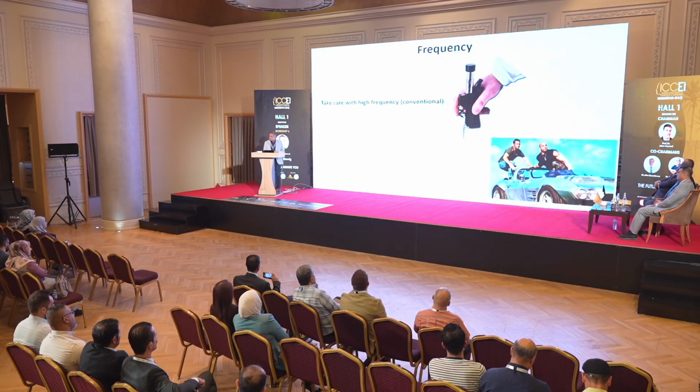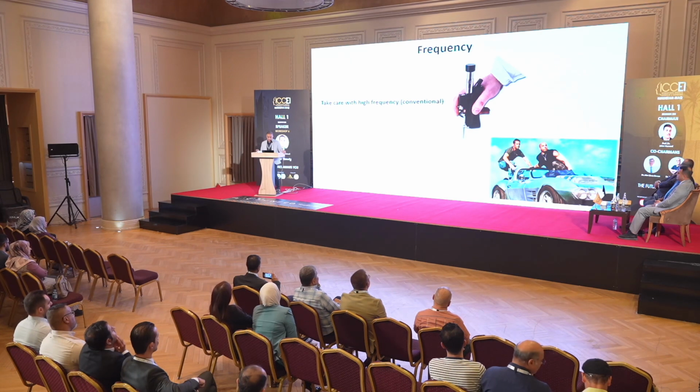Let's go to frequency. Frequency means the repetition rate, how many pulses can be generated by your handpiece. Take care with high frequency, please, because high frequency needs a professional to handle it, moving in correlation with the repetition rate. So the ideal is to make an overlap of about 10%.